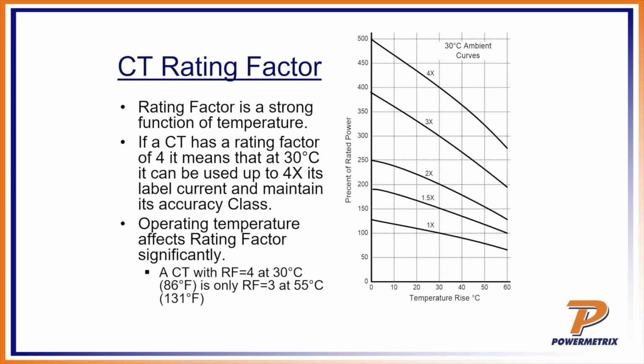So if a CT has a rating factor of 4 at 30 degrees C, it says right there on the nameplate, it can be used up to 4 times its label current and maintain its accuracy. So you can see right there at the bottom, it says a CT with a rating factor of 4 at 30 degrees C, 86 degrees, is only a rating factor of 3 at 55 degrees C. See how much I bumped up my current. So this definitely affects you when you're trying to design something out in the middle of the desert in Arizona, versus in nice, cool mountains up here in Tennessee. So, yeah, it definitely affects the rating factor. So you have to consider that temperature, because you may get a derating and think you've got a rating factor you actually won't see out there at the site because of the temperature.